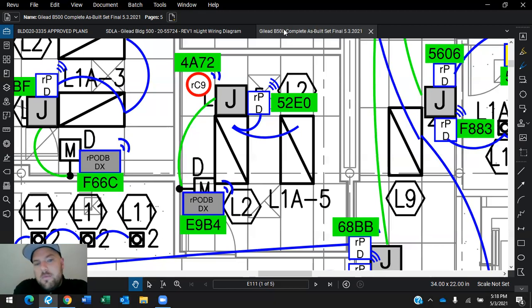Also keep in mind, when we're roping the MC, we have to make sure we're strapping it, putting the bat wings on, installing the J boxes appropriately, using ground tails in our boxes per the NEC, making sure we're tying off our light fixtures and screwing them off if that's required. Every single one of our lighting installations needs to be like that.